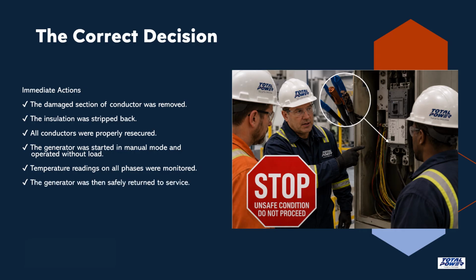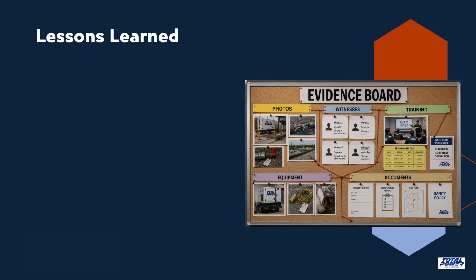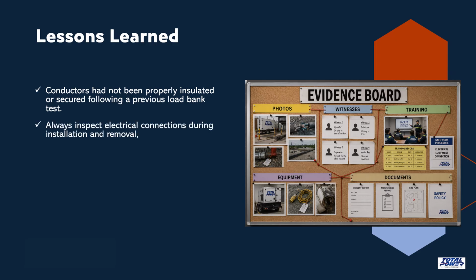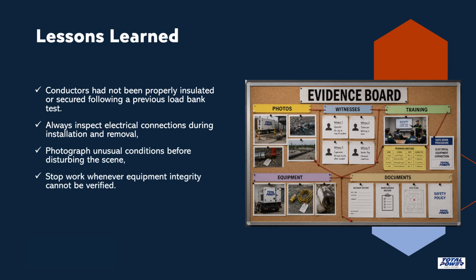Although the immediate hazard had been addressed, the near-miss investigation was only beginning. The investigation could not confirm the exact cause of the failure, but the most likely contributing factor was that the conductors had not been properly insulated or secured following a previous load bank test. Several important lessons were identified. Always inspect electrical connections during installation and removal, photograph unusual conditions before disturbing the scene, and stop work whenever equipment integrity cannot be verified.